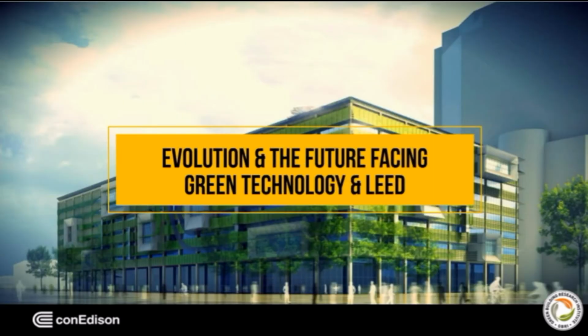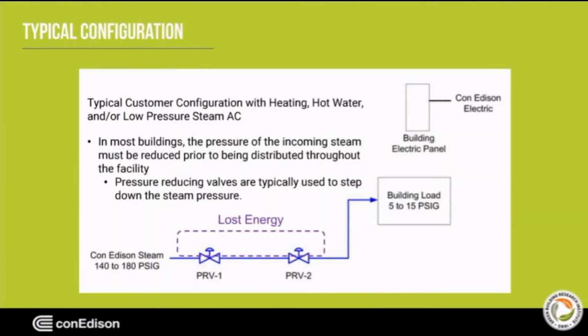In the next section, I will speak briefly about 3 companies that provide technologies that allow a customer to generate electricity while simultaneously reducing the pressure of incoming steam. When steam enters a customer's building, it is typically between 140 to 180 psi. Our customers typically use pressure-reducing valves, or PRVs, to lower the pressure of steam in order to be distributed throughout the facility. As steam is passing through the PRV and the pressure is being reduced, some energy is also being wasted.